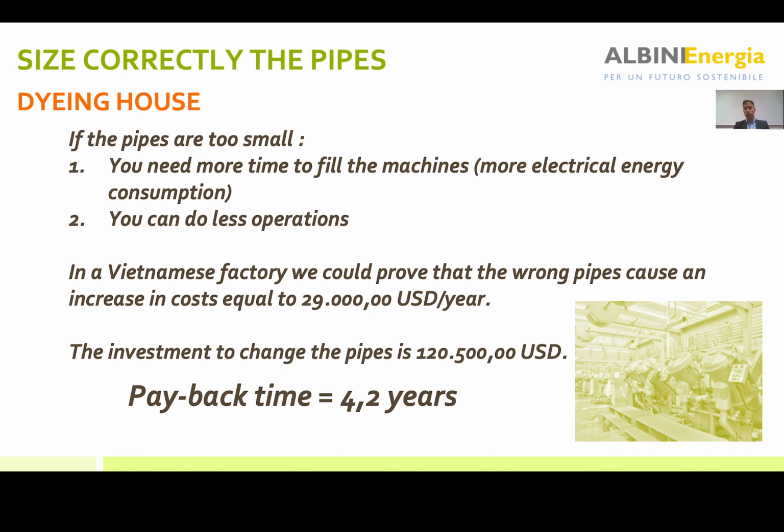So according to all those diagrams, we were able to calculate the time that they lost waiting to fill the machine, drain the machine, heat the machine, and reduce the temperature inside it. And so at the end, the final cost just related to the mistake that they made in the connection of the machine could be calculated at almost 30,000 US dollars.